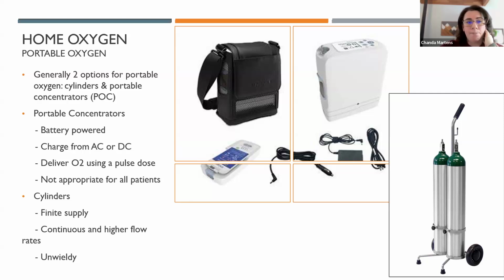They're not appropriate for everybody because they deliver their oxygen with a pulse dose, which means you have a cannula that you wear in your nose. When you take a breath, you cause a drop in pressure in the tubing that triggers that little machine to give you a puff of oxygen, a little burst. That can be adjusted so that the puff is actually bigger or smaller. But for some people, that pulse dose just isn't quite enough to hold their oxygen levels up. They need the continuous flow of oxygen that they would get from something else. So in order to have one of these, best to be assessed by an RT or an RN to make sure that, number one, you can in fact trigger it. And number two, it's enough to hold your oxygen levels up.